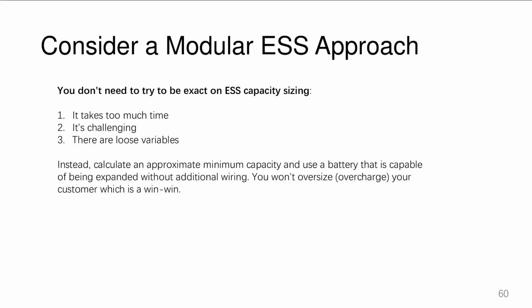There are a lot of variables, so it's hard to be perfect. But if you can do a modular ESS system, you can install something that isn't oversized, and if the customer needs more, you can add another battery module without requiring rewiring. Or maybe you buy two small stacks with batteries in parallel, and each stack can get another module if necessary. This way you don't risk oversizing and overcharging your customer, so a modular approach is a win-win for you and the customer.